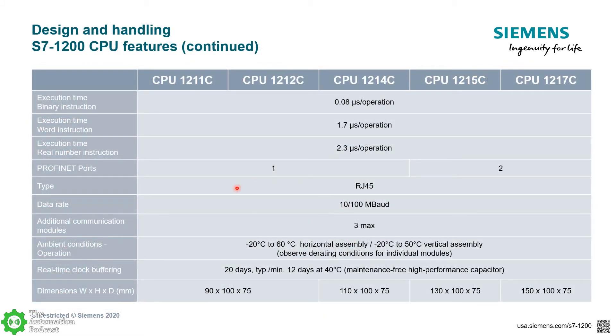One thing worth pointing out is processing speed. Siemens doesn't advertise an overall speed or cyclic update rate because it depends on what you're doing in your program — it's specified per instruction type. With the S7-1200, you get about 80 nanoseconds processing speed for binary or Boolean instructions such as normally open/normally closed contact operations. Word instructions — like moving registers, bytes, or words — run at 1.7 microseconds per operation. Floating-point math and arithmetic operations run at about 2.3 to 2.5 microseconds.